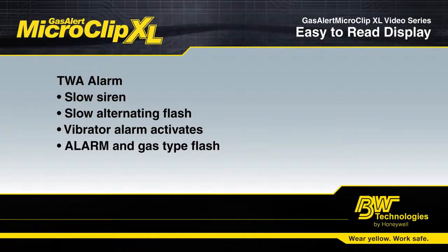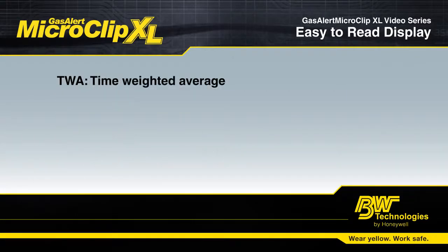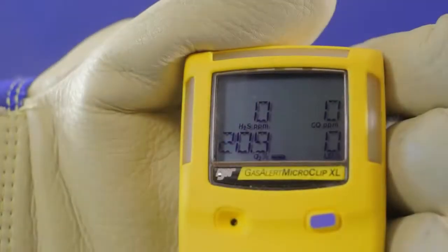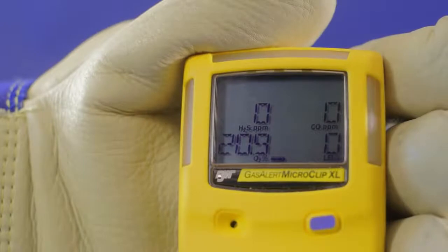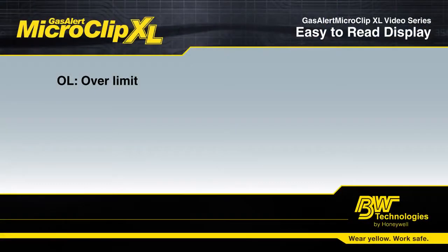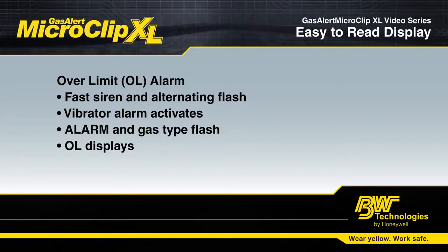Like STEL, TWA alarms are also calculated for toxic gases. A TWA alarm signals a cumulative exposure over time, typically an 8-hour period. TWA stands for Time Weighted Average. If you are taking proper action and evacuating any time a low or high alarm is sounded, your Gas Alert Micro Clip XL should not go into STEL or TWA alarm. The fifth type of alarm is an OL, or Over Limit Alarm. This means that the level of gas in the environment is beyond what the sensor can measure. OL will flash in place of the reading of that sensor.